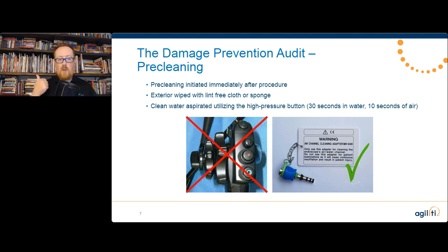You're definitely going to want to wipe down that exterior with a lint-free cloth or sponge. And of course, aspirating the water using the high pressure button if this is an Olympus scope. But whatever that aspiration of the cleaning media is, the pre-cleaning part of the IFU will specify what that specifically is.